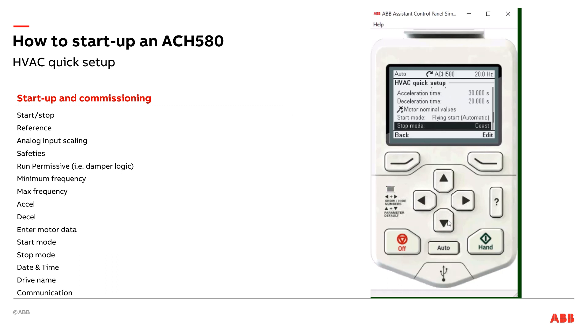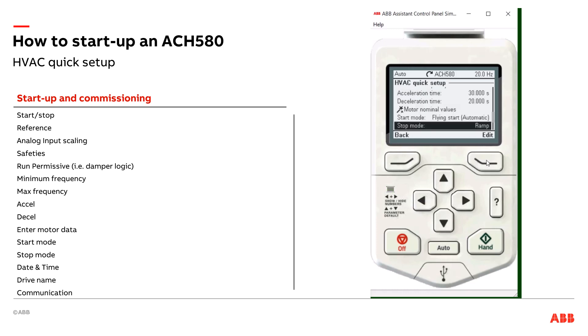You've also got your stop mode — this is where you choose whether you want to coast to a stop or ramp to a stop. Application-wise, for fans I typically coast to a stop. For pumps, I'm going to set that to ramp to a stop, because the last thing I want is to tell the drive to stop and get that pump whack and water hammer effect. So that's why for pumps you ramp it to a stop.